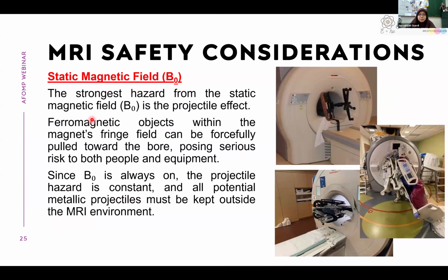For the static magnetic field, the strongest hazard is actually the projectile effect. Ferromagnetic objects within the magnet's range can be forcefully pulled towards the bore, so it poses a serious risk to both people and the equipment itself. Since the static magnetic field is always on, the projectile hazard is considered constant, and all potential metallic projectiles must be kept outside the MRI environment.